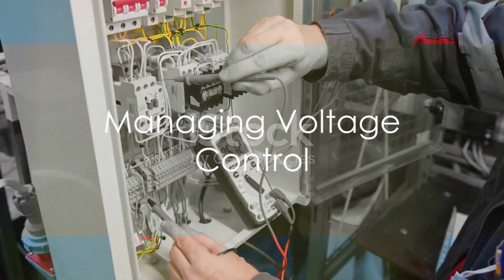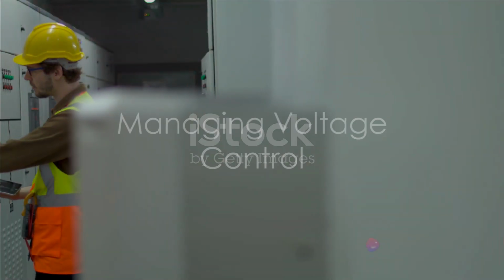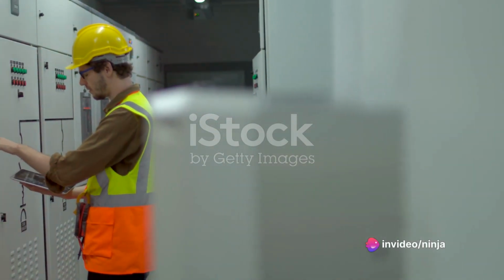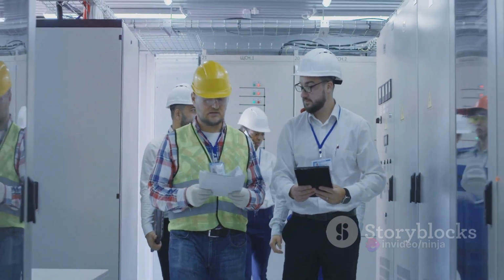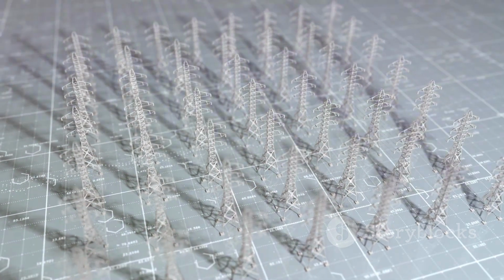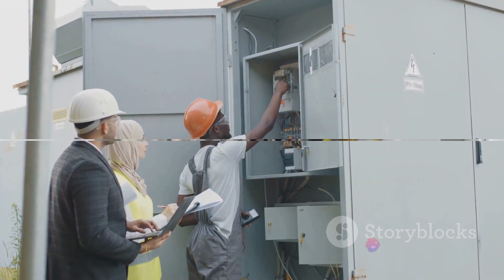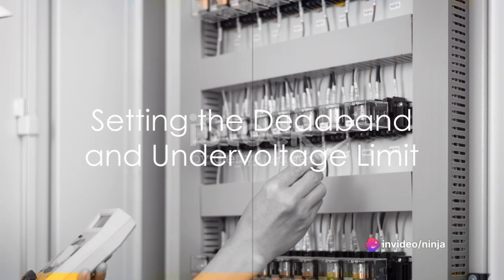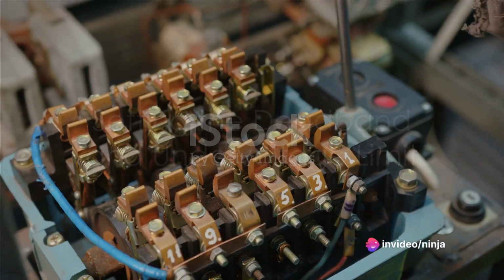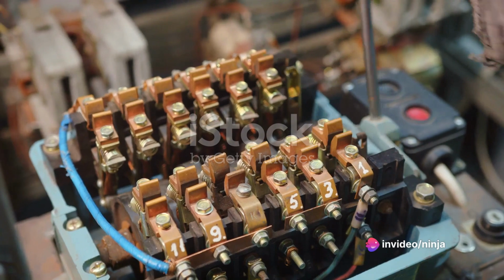But voltage control isn't a free-for-all. It must be carefully managed to stay within an undervoltage limit and an overvoltage limit. These limits are the subject of ongoing discussions, but regardless of the specific numbers, the basic coordination principles remain the same. The deadband is typically set slightly above the nominal voltage to accommodate for voltage drop along the feeders.